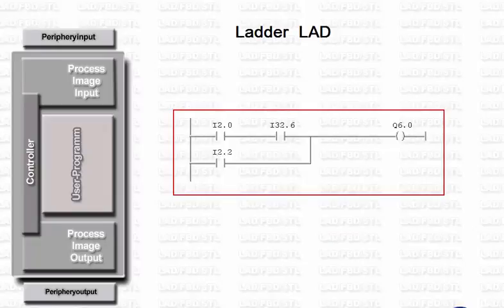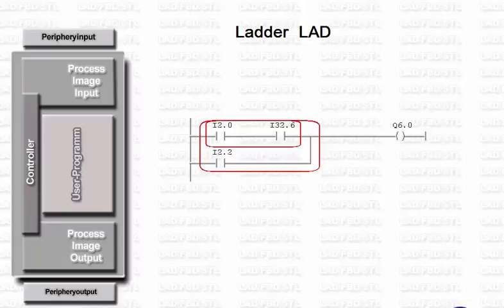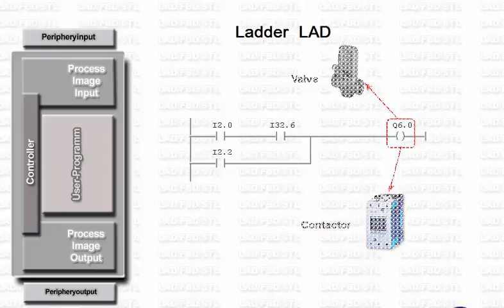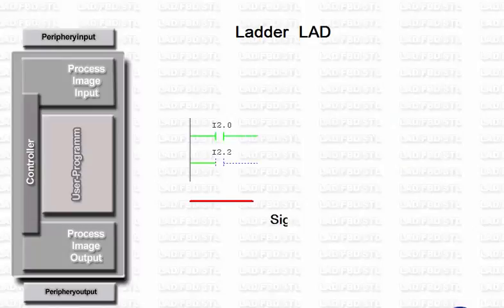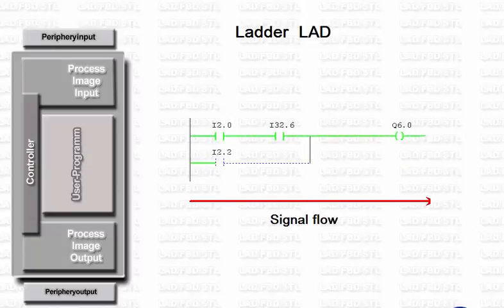In LADDER, the binary combination portion of an automation task is implemented by series and parallel connections of contacts. As in an electrical circuit diagram, each such connection is terminated by a coil which represents the output to an actuator, such as a valve or a contactor. The current, or better signal flow, runs from left to right as seen by the user.